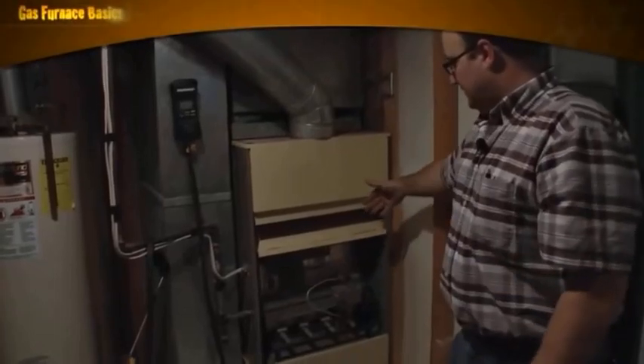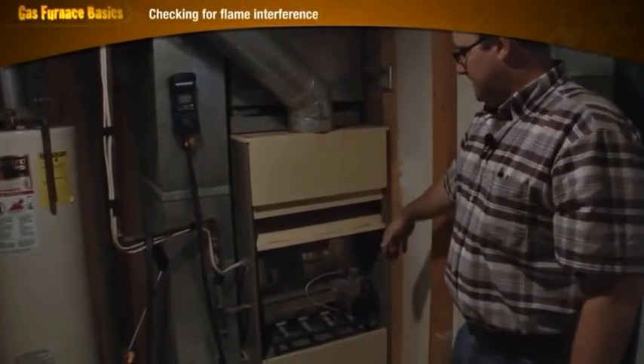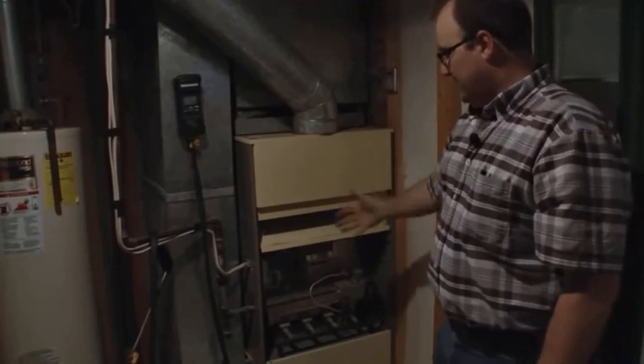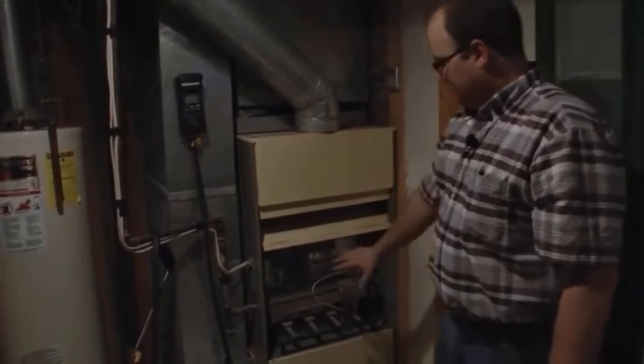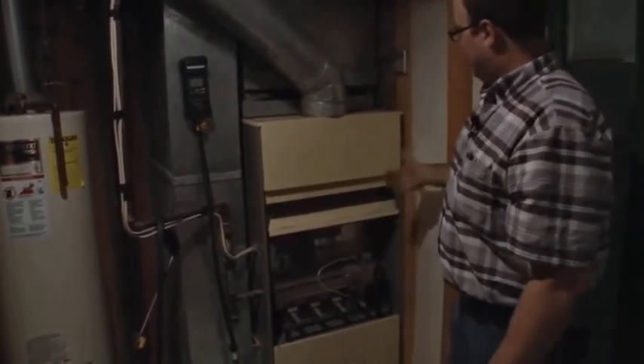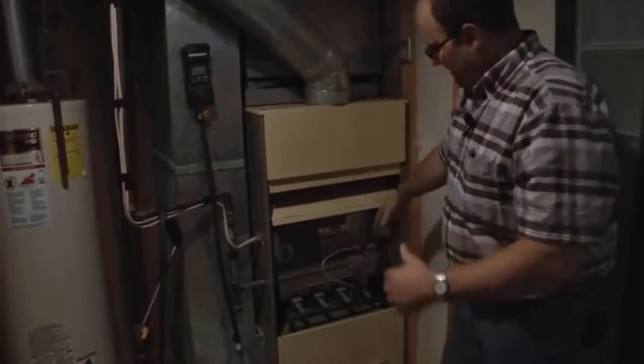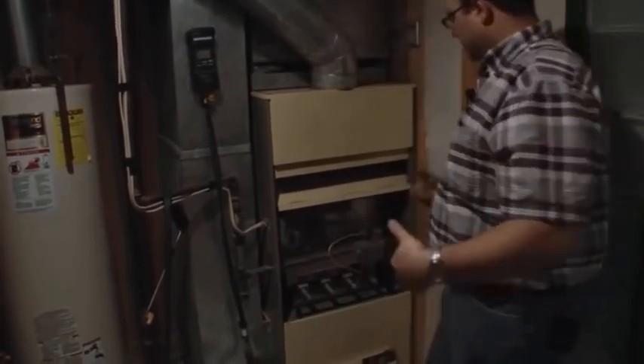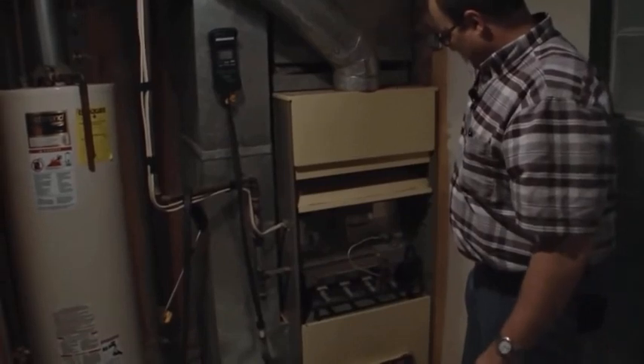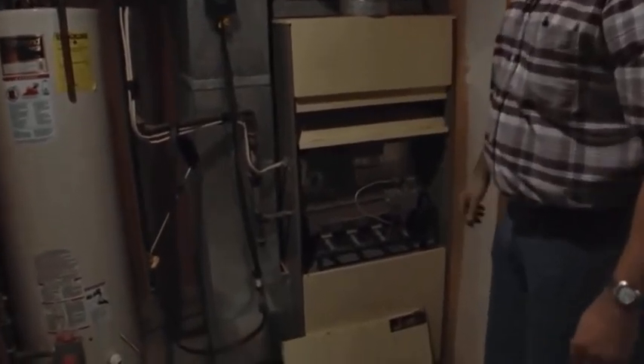One of the things I could kind of hear on this furnace is, I'm pretty sure it has some flame rollout. So we'll take the cover off here. I will go ahead and start it, and we'll see if this fills up with flames when this thing first starts. Okay, so there's a little bit of flame rollout on that, not too much, but there is a little bit.